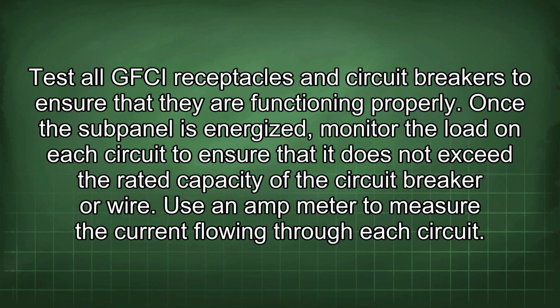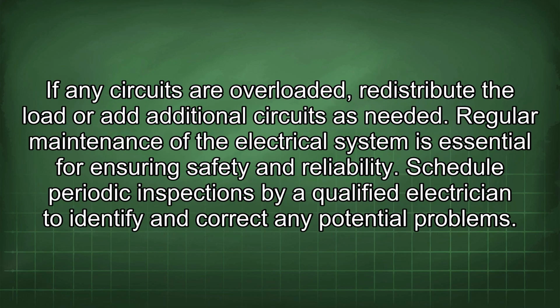Once the subpanel is energized, monitor the load on each circuit to ensure that it does not exceed the rated capacity of the circuit breaker or wire. Use an amp meter to measure the current flowing through each circuit. If any circuits are overloaded, redistribute the load or add additional circuits as needed.